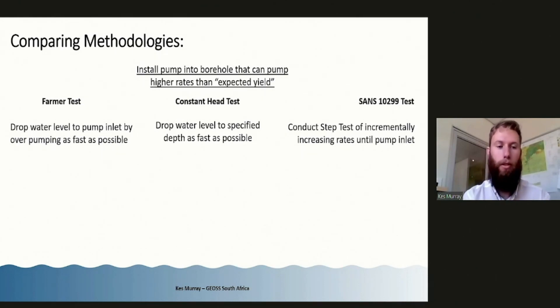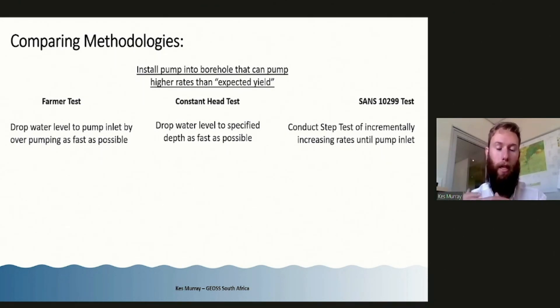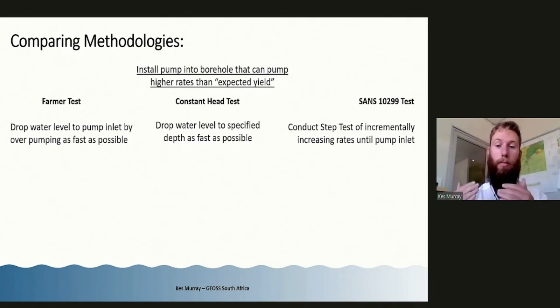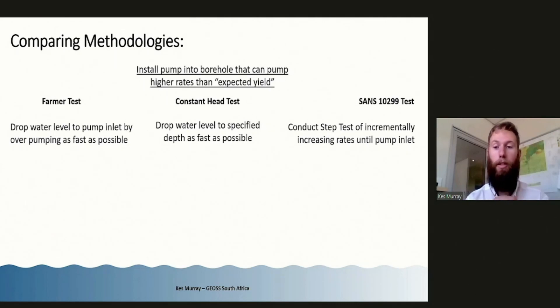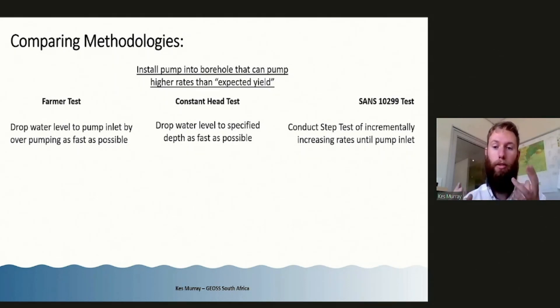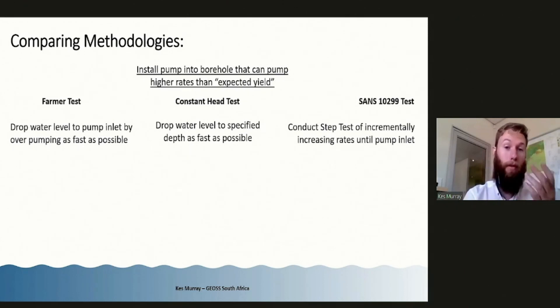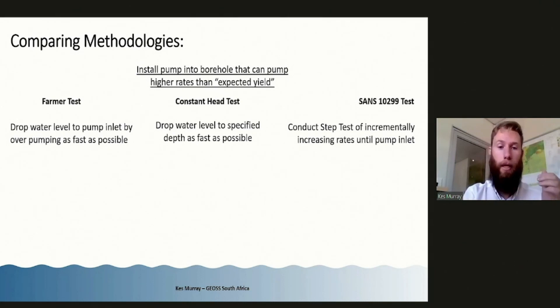In the Farmer Test, what is essentially done is the water level is dropped to pump inlet as fast as possible. In a constant head test, the main distinction is just that it's pumped to a specified level as fast as possible. Whereas in SANS 10299 testing, we're normally talking about doing a step test first, or even a calibration test before that, to look at what the water level starts doing at different pumping rates.